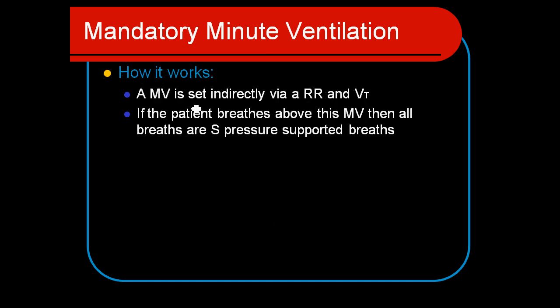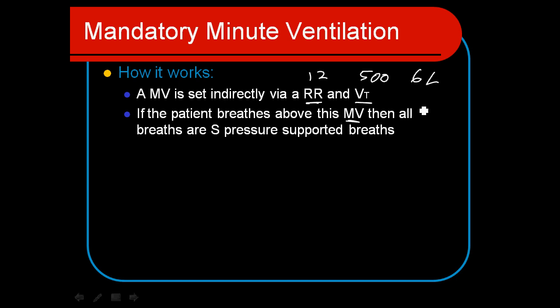The minute ventilation is set indirectly via the respiratory rate and tidal volume, just like on a regular ventilator. For example, a rate of 12 and a tidal volume of 500 mL establishes a minute ventilation requirement of six liters. As long as the patient keeps breathing above that six liters per minute, they're going to just receive regular pressure support with no mandatory or assisted breaths whatsoever.